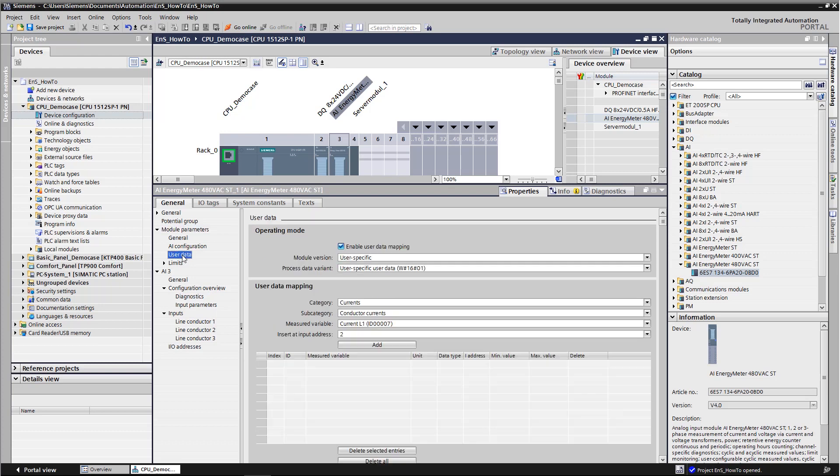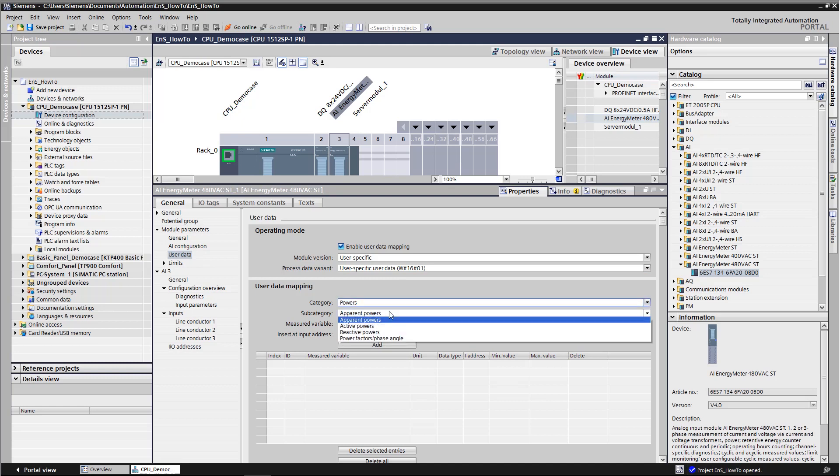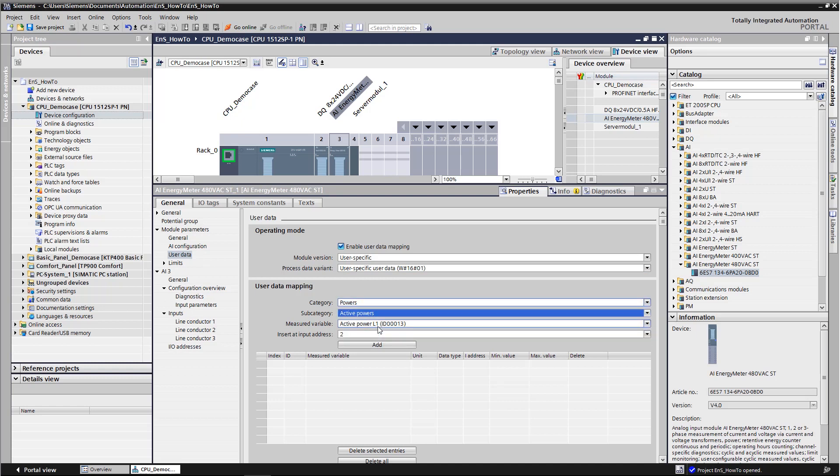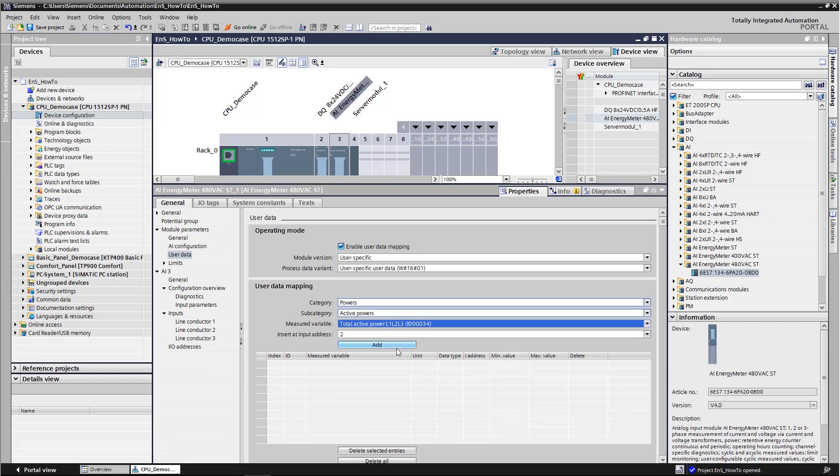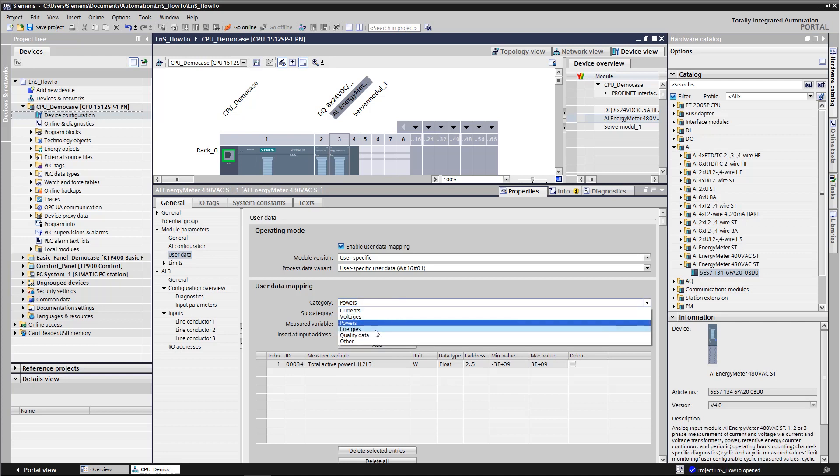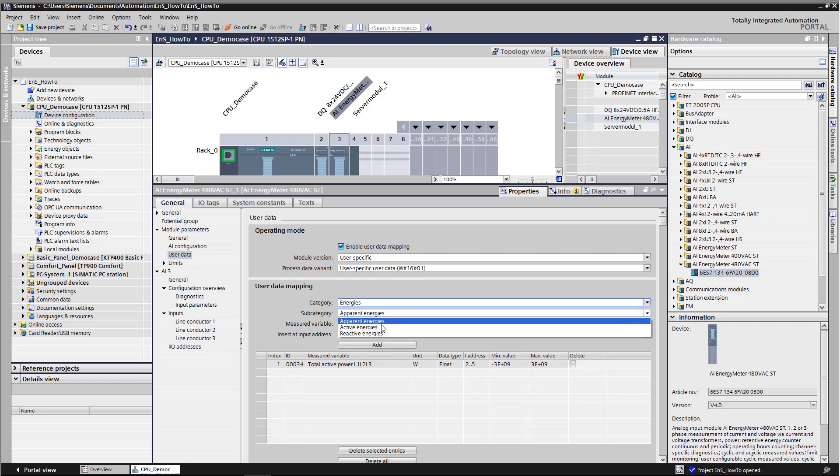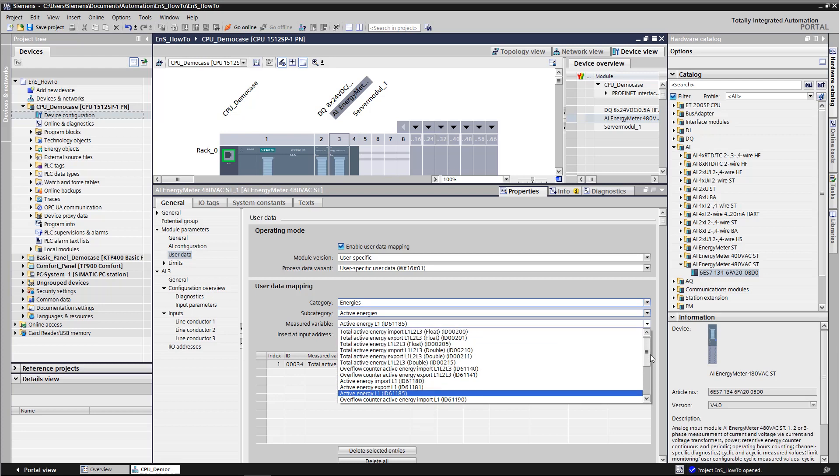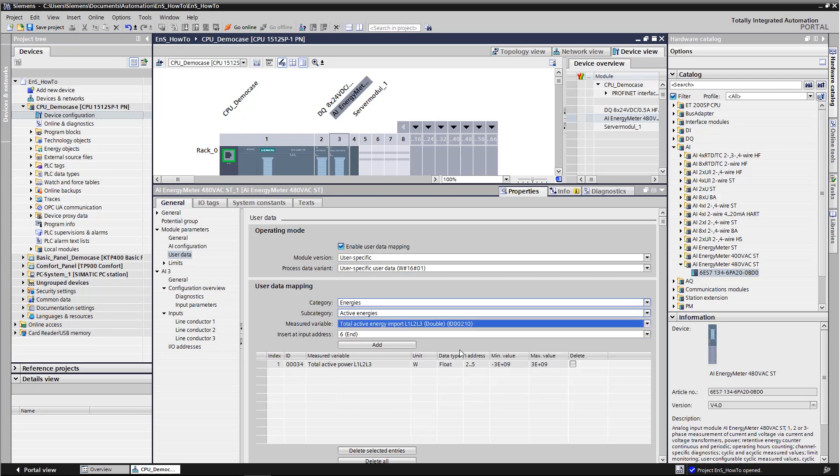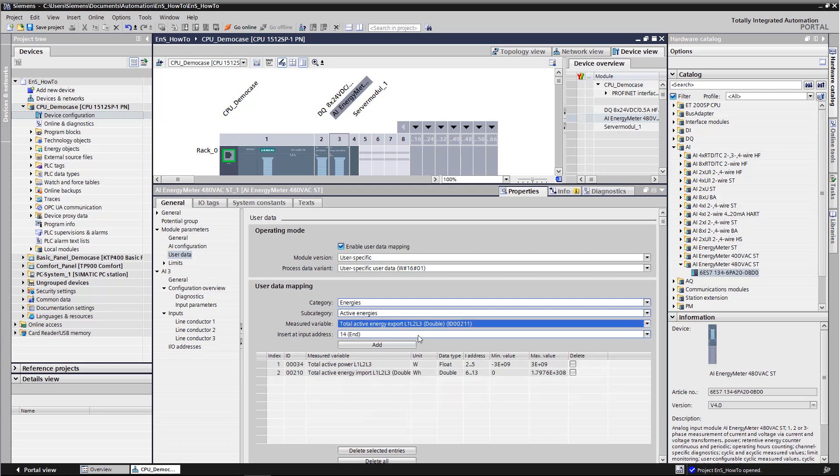Three parameters are required for the basic data. First, the total active power identified as ID 34 under the category powers. Then the total active energy import ID 210 under energies. Finally, the total active energy export ID 211 is created under energies.